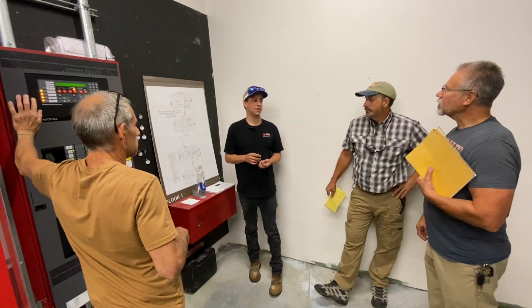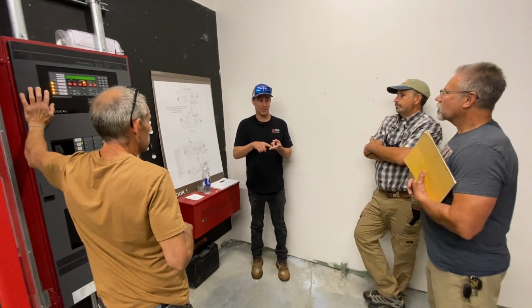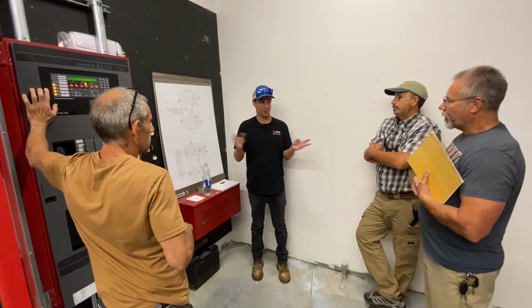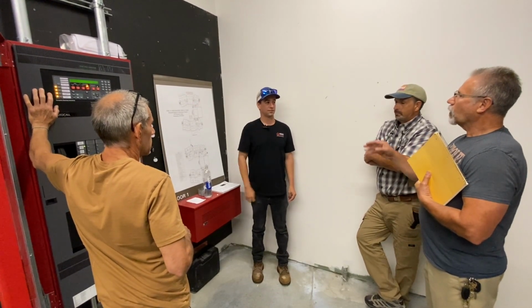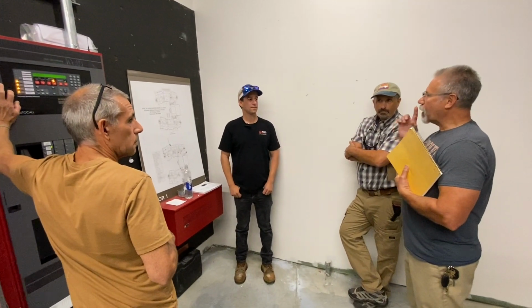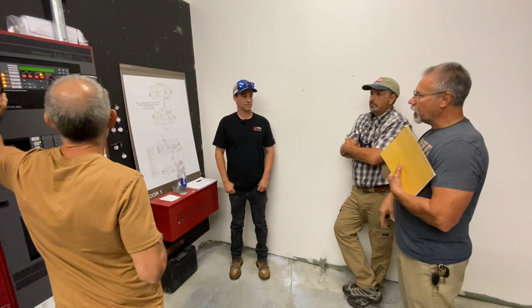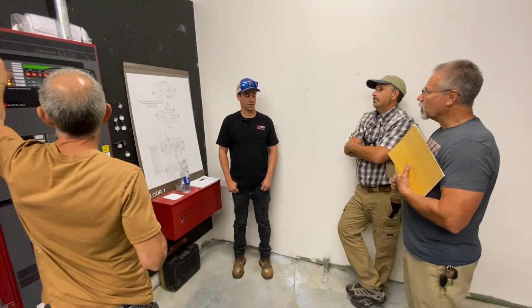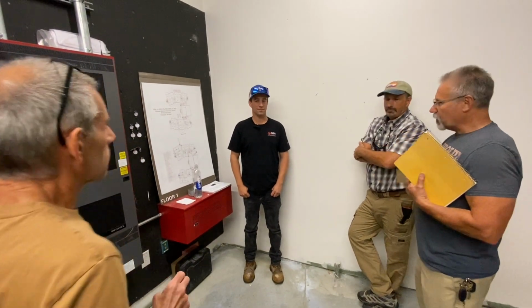Here's the way I like to do fire drills. You set off the alarms, and you still let the doors drop, because that's going to happen when there's a fire, and the kids should know that the doors go. But elevator and HVAC will not do anything. Right, that's what our other schools do. They do the same thing. Drop the magnets. Horns go off. Does not do elevator capture. Does not drop out HVAC. Correct. I'm good with that.